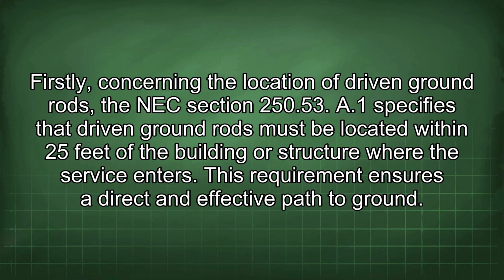Firstly, concerning the location of driven ground rods, NEC section 250.53(A)(1) specifies that driven ground rods must be located within 25 feet of the building or structure where the service enters. This requirement ensures a direct and effective path to ground.